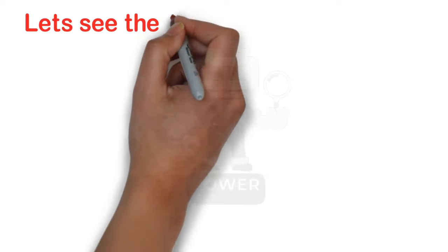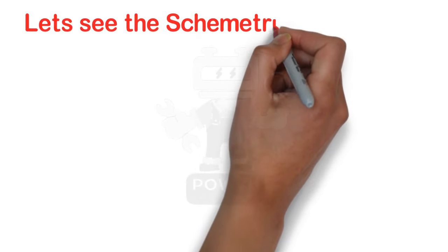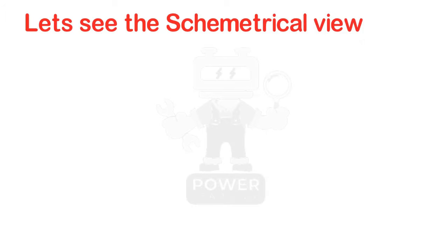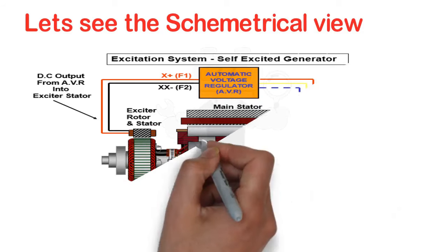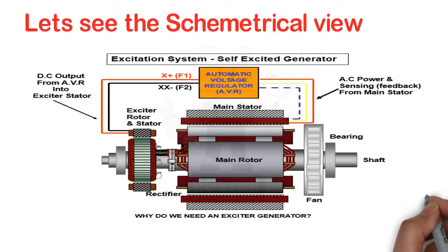Let's see the schematic view. In this simple self-excited generator, it takes AC power sensing feedback from the main stator, gives it to the Automatic Voltage Regulator (AVR), and the regulator gives the output as DC — two wires, positive and negative — to the exciter rotor and stator. After that, the diodes convert the three-phase AC supply into DC and connect it to the main rotor.